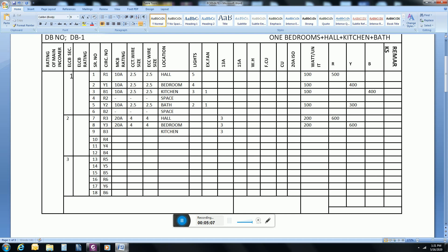For the kitchen sockets, there will be three sockets. The breaker size here will be 32 ampere, wire 4mm, ECC 4mm. Remember that in the kitchen we always use 32 ampere because there will be a ring circuit. Normally if we use more than three sockets the breaker size will be 30 ampere, but in the case of a kitchen the breaker size will be 32 ampere and there will be a ring circuit. The load on the blue phase will be 600 watts.